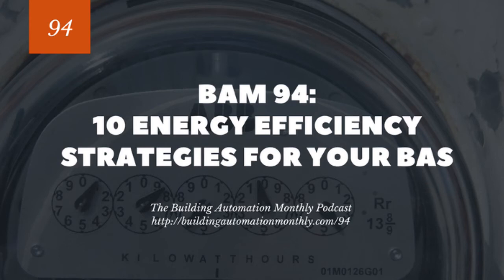Or where are you putting your 2/3 sensor? Is it actually 2/3 down the longest duct, or is it actually at a point where you're getting a good distribution of unit types? Meaning you've got VAV units and you're looking at, I've got some reheats, I've got some cooling onlys, I've got some fan power boxes. I want to get a good distribution. Or do you simply want to do the 2/3? It just depends on your control strategies.